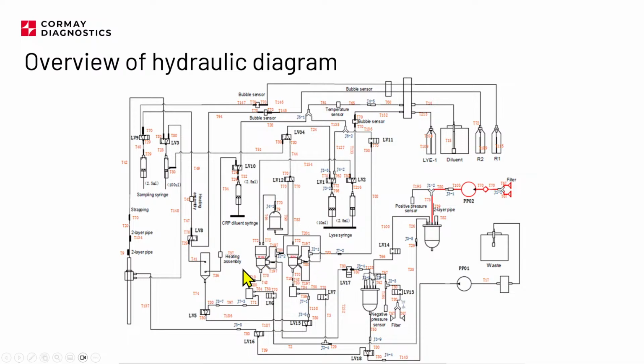What does the analyzer need in order to make measurements and perform everything automatically? We need to have a way to supply diluent and lyse, diluent to the RBC, right? We also need a way to remove those liquids from the chamber. So the bottom port and this three-way isolation chamber are here because of that. We are removing liquid through this port, through this isolation chamber, and this waste circuit through this valve, and through the pump into the waste.